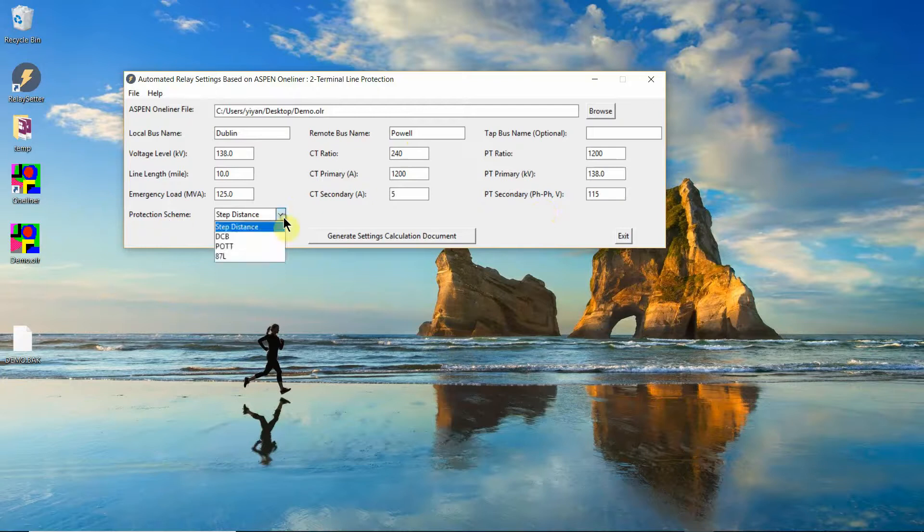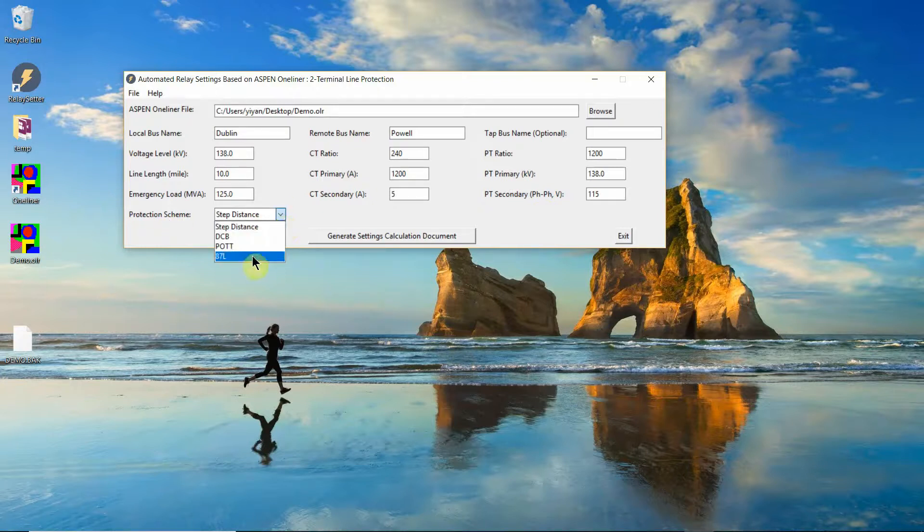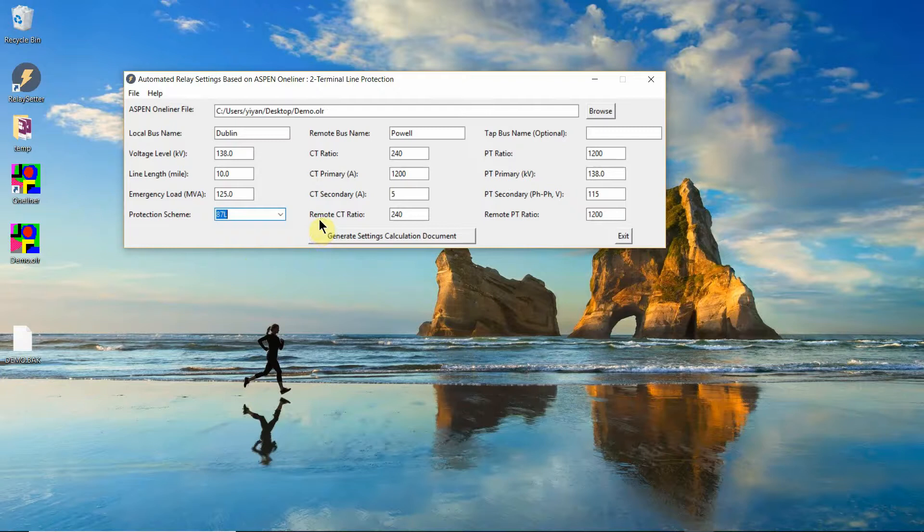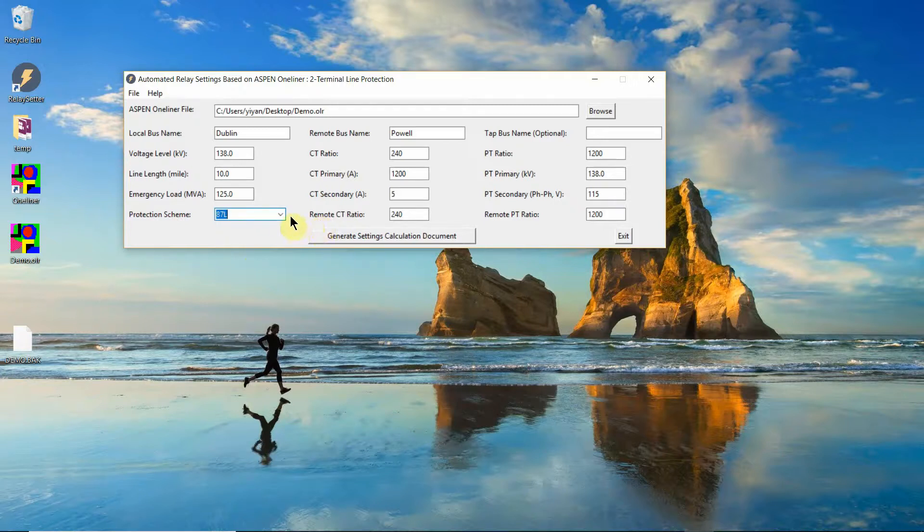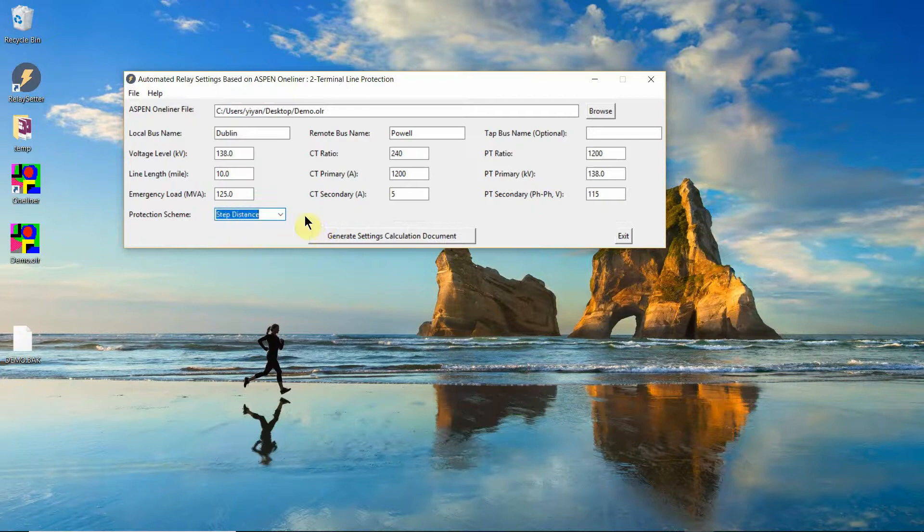So there are four schemes. If you select the current differential scheme or DCB scheme, you need to enter the remote CT ratio and the remote PT ratio because there are some coordination that are necessary for those schemes. So let's try a step distance scheme.